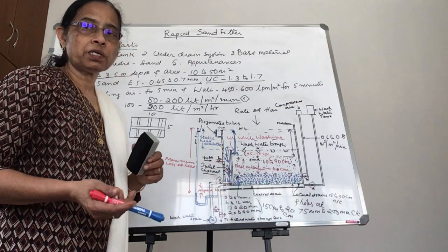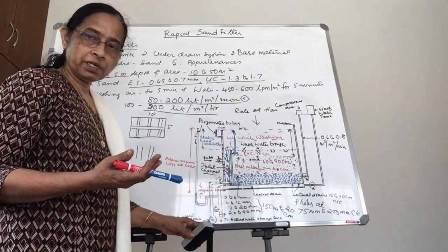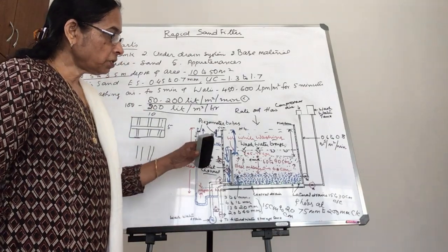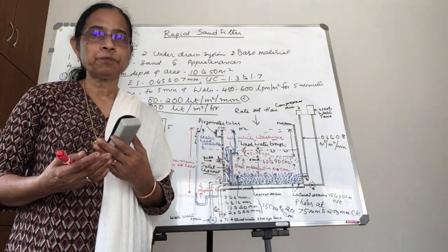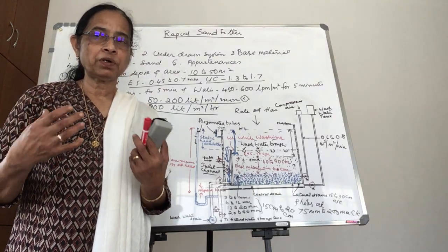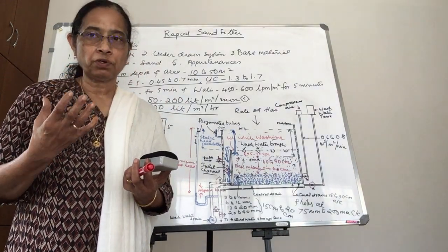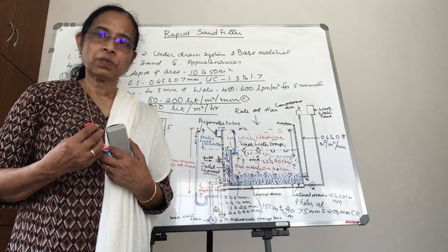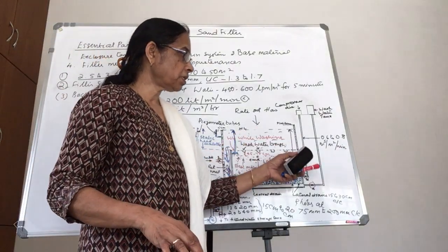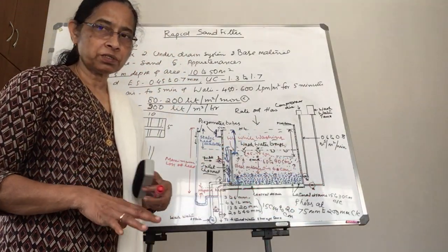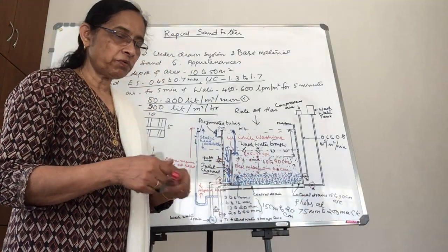Now the entire water which is coming through the inlet channel is collected to the drain pipe and let out. Once we continue this process for 4 or 5 or 6 minutes, you can observe that the entire dirty water has been removed. Now the water which is there in the sand media is almost clean, almost all dirt is removed. And now you can stop this backwash system. You can close valve 6, which we closed earlier, and now we are closing valve 4 also.